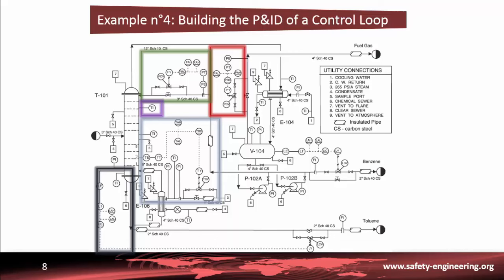The distillation column has three control loops: the reflux flow, the temperature at the bottom of the column, and the level within the column. As you can see, all controllers can record data such as the measured variables, the output data for control valve, etc. Some sensors are placed into the process just to have a look at particular physical data. For example, TI at the top of the column, it is just an indicator and is not incorporated into a control loop.